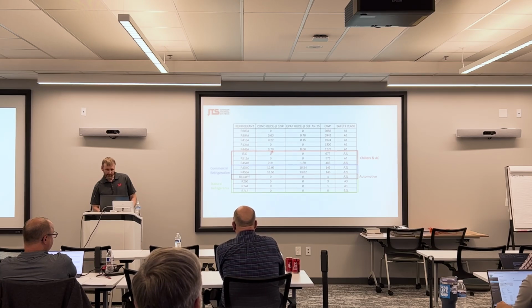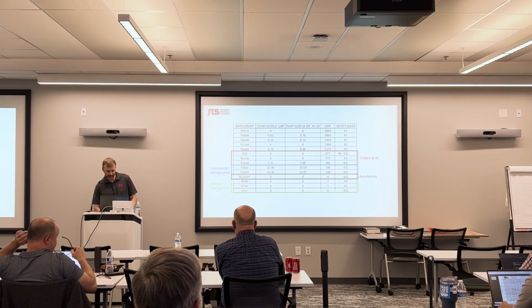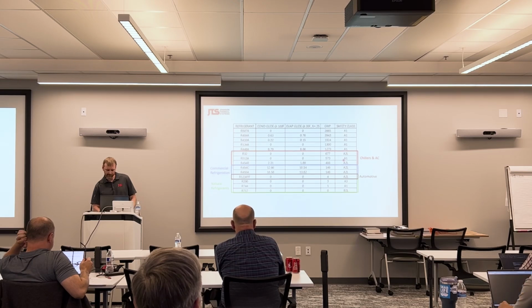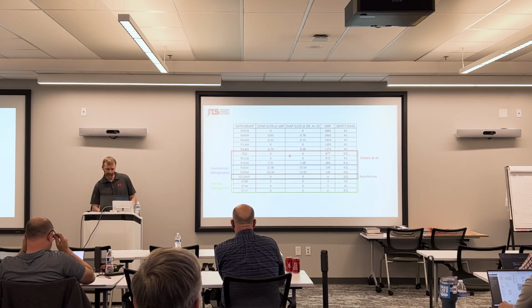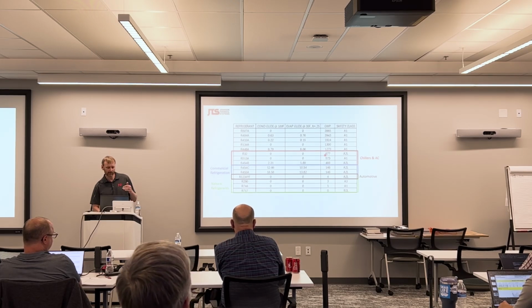448A, it's probably the one that we've used the most in the last 5 or 6 years. It's got about 8 degrees of glide. 1273 GWP, it's an A1 refrigerant. Where we're seeing the transition in chillers and air conditioners, we're seeing a lot of movement over towards R32, which is an A2L refrigerant. It's a pure refrigerant, so it doesn't have any glide. GWP of 677, so it's below that 700 GWP limit.